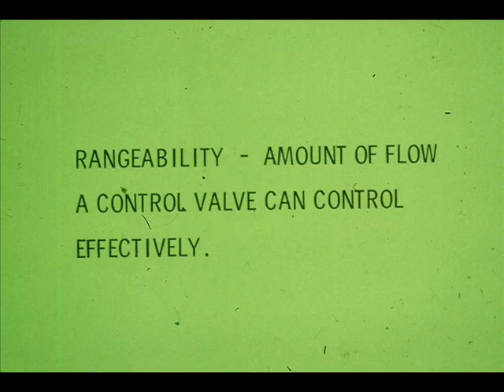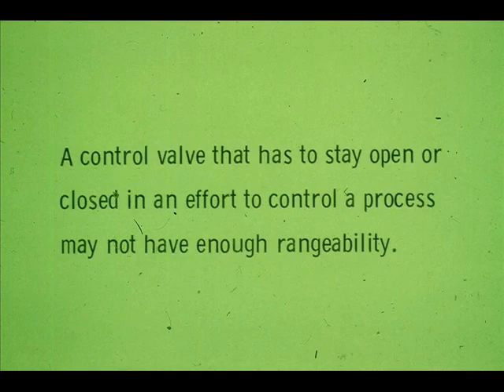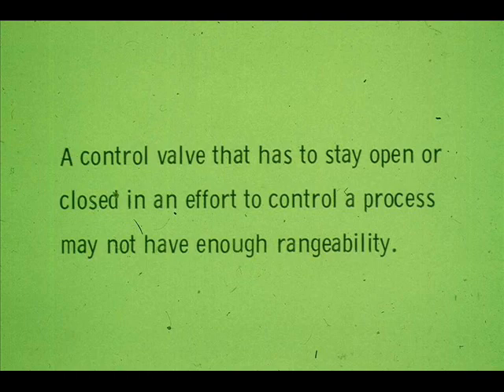Rangeability refers to the minimum and maximum amounts of flow a valve can control effectively. Rangeability is related to Cv, trim characteristic, and process conditions. Sometimes a control valve has to stay open or closed most of the time in an effort to control the process. This may indicate a valve malfunction, but often it means the valve is being used out of its effective controlling range.